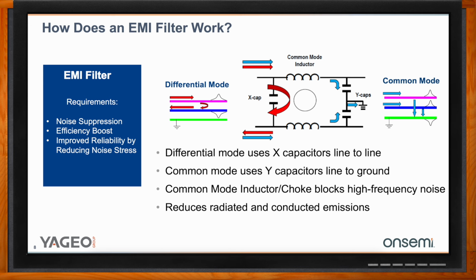One thing that's also really important about the EMI filter is what happens when it fails, because if a failure occurs, they need to prevent any type of shock or fire. That's why oftentimes X or Y capacitors are actually referred to as safety capacitors.